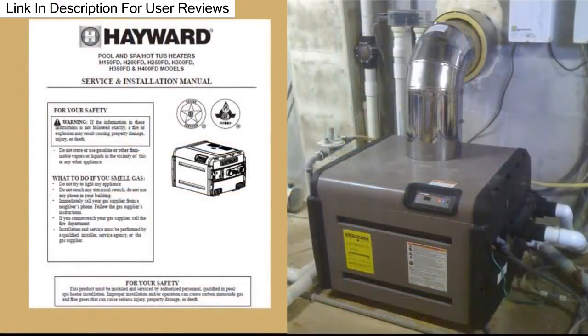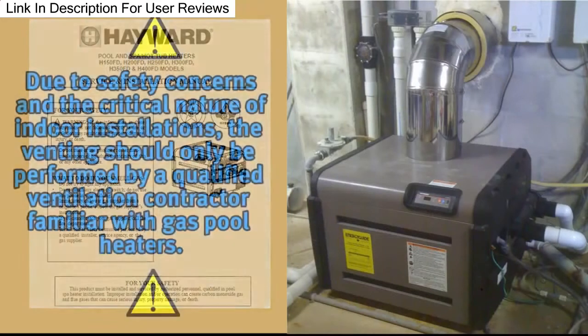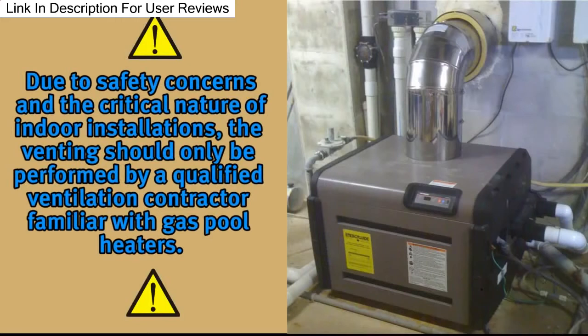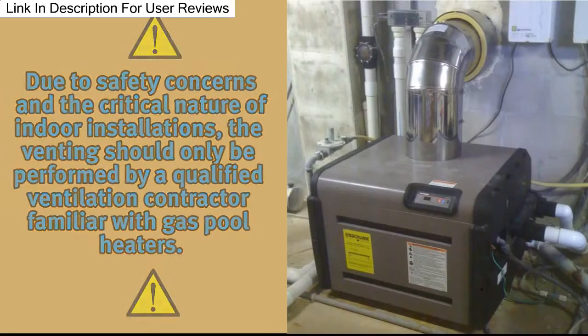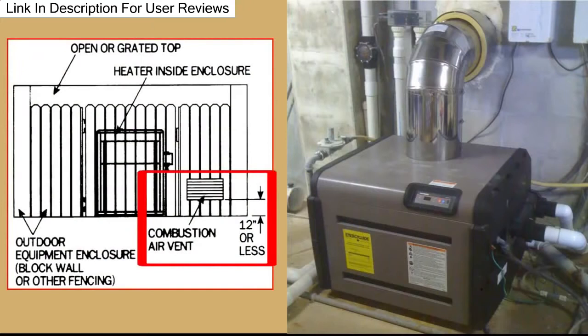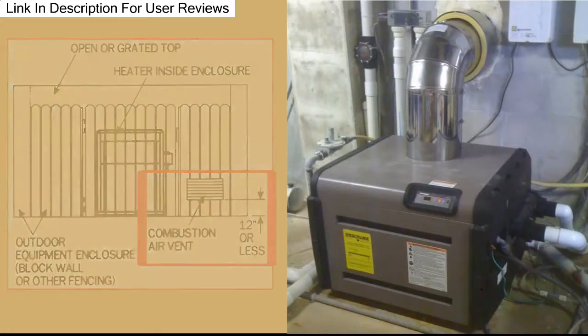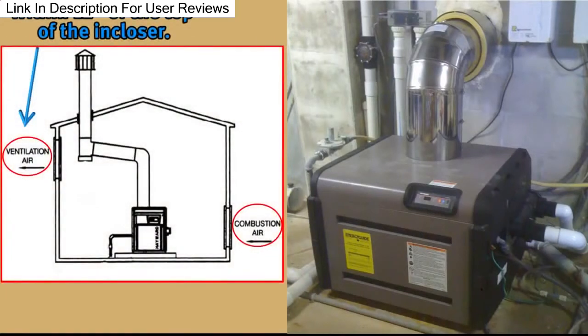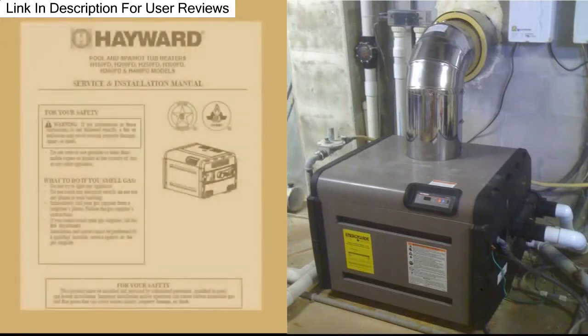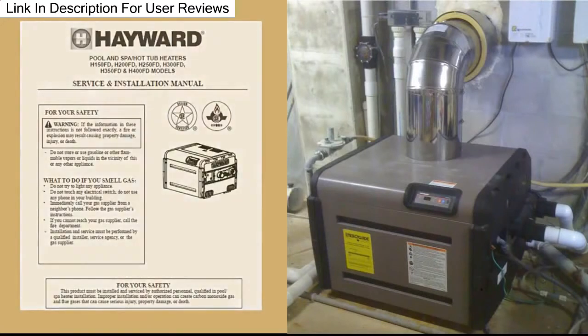If the heater is to be installed indoors, consult the installation manual for venting instructions, keeping in mind that due to safety concerns and the critical nature of indoor installations, the venting should only be done by a qualified ventilation contractor familiar with gas pool heaters. If the heater is to be enclosed or installed indoors, it must have a combustion air vent commencing within 12 inches of the bottom of the enclosure. A ventilation air vent will be needed if installed indoors, commencing within 12 inches of the top of the enclosure. See the installation manual for specifics on this type of installation.